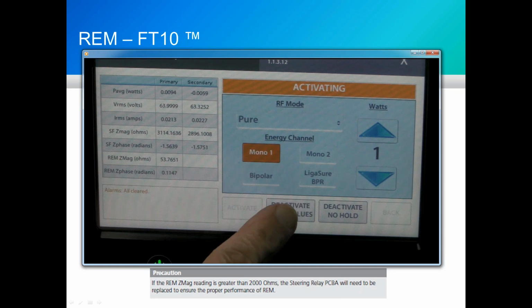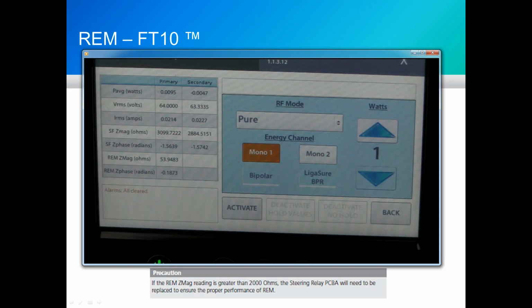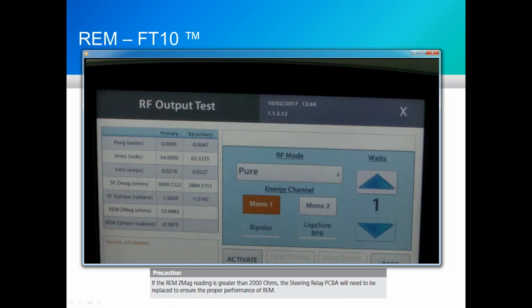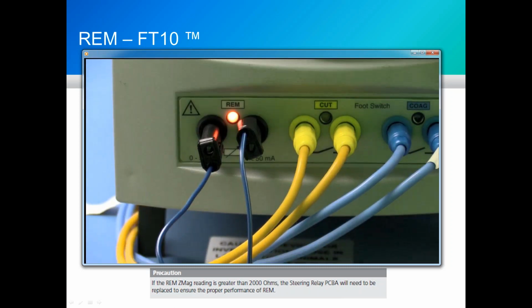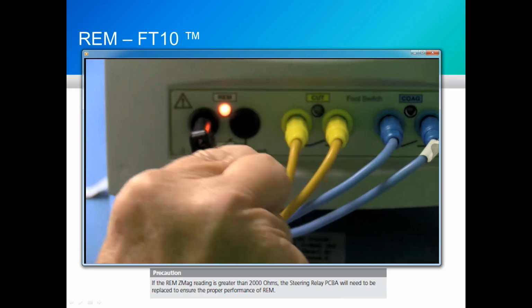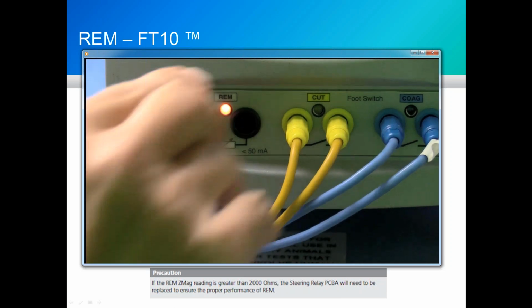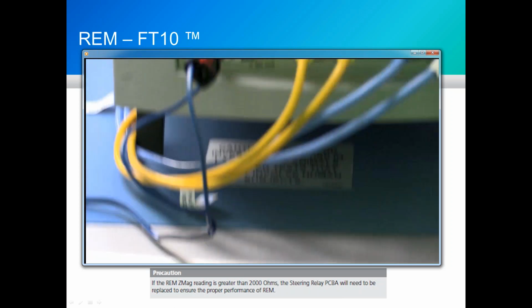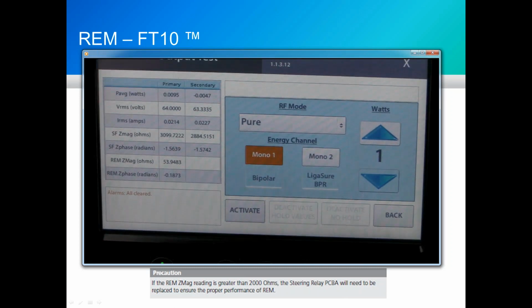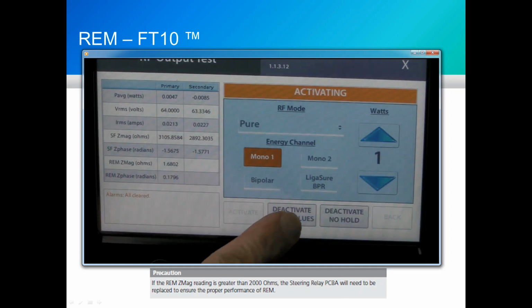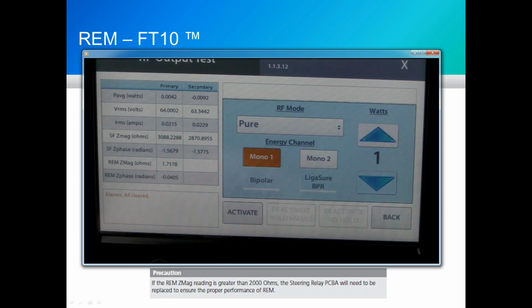Toggle the generator. And we measure just under 54 ohms. Now I'm going to short the patient return cable. And we measure 1.7 ohms in the shorted condition. Here we're just really seeing the resistance of the cable itself.